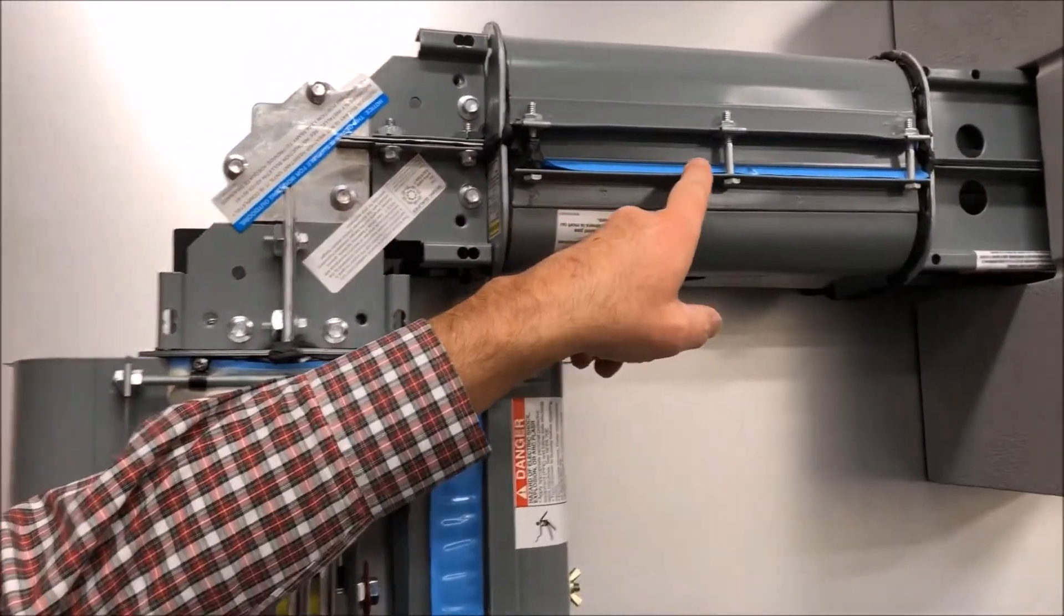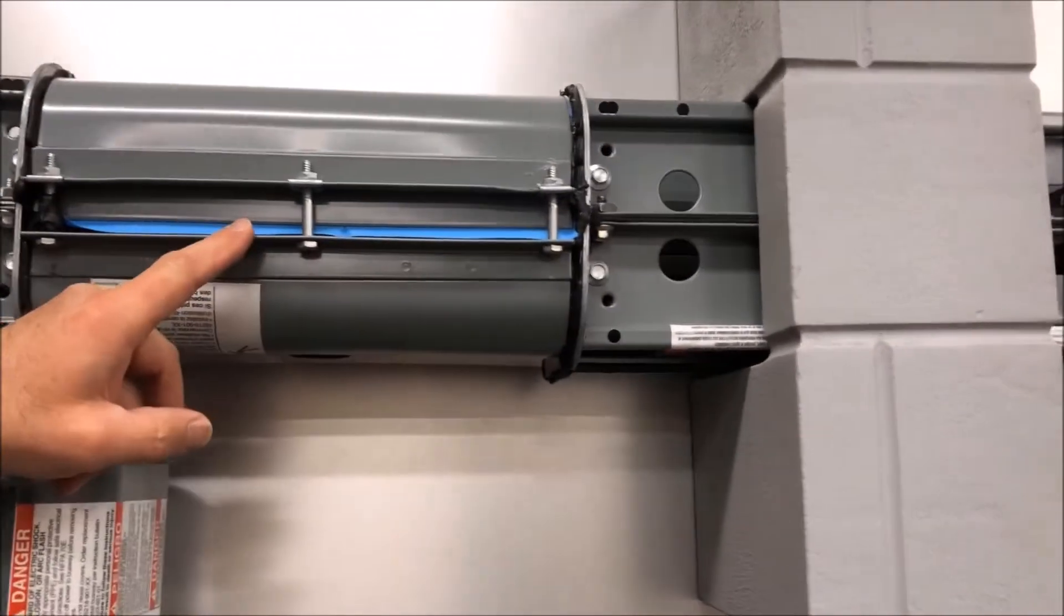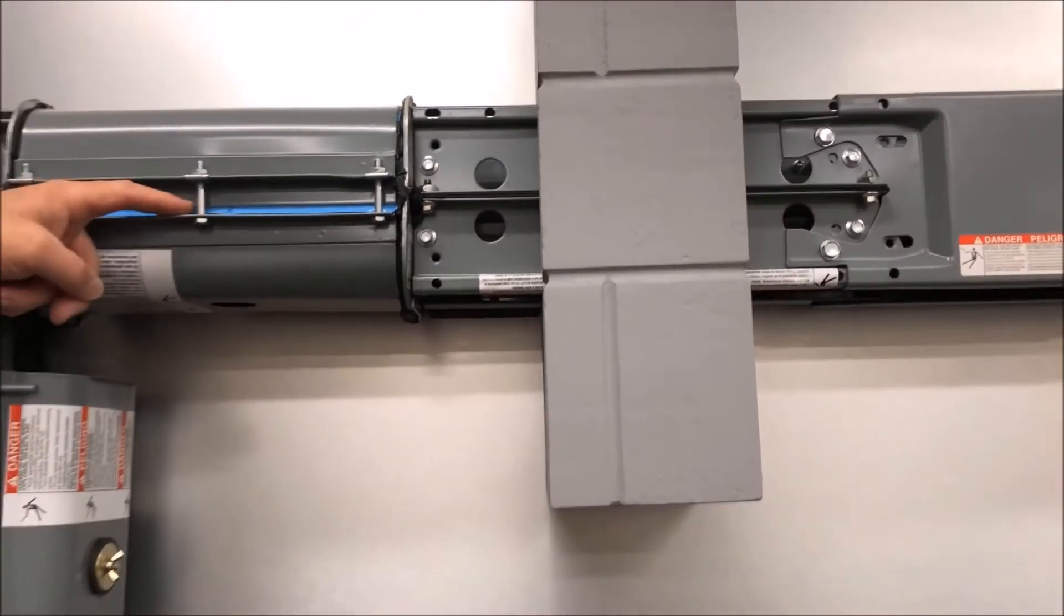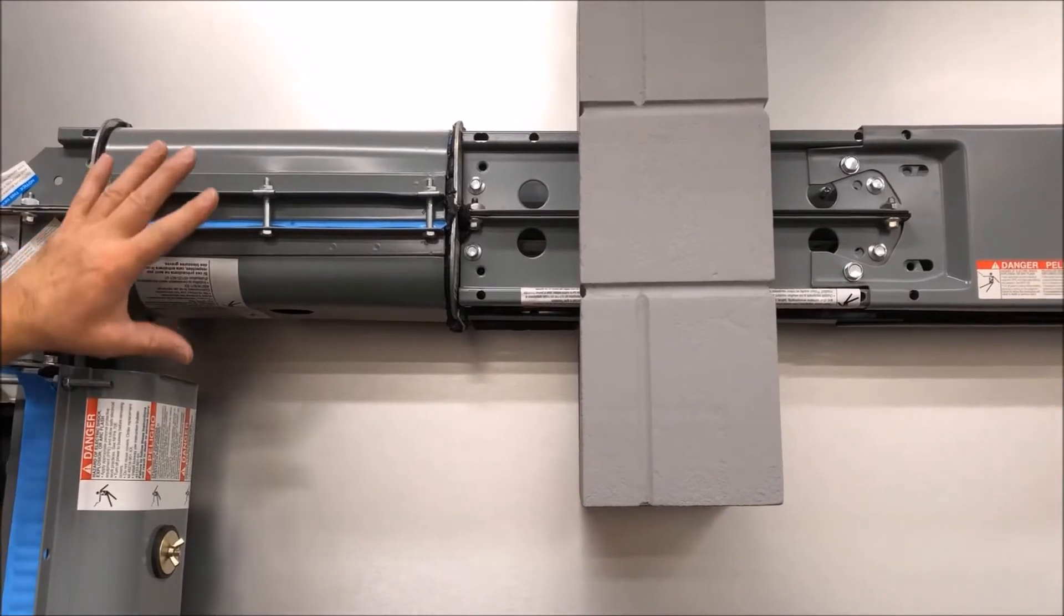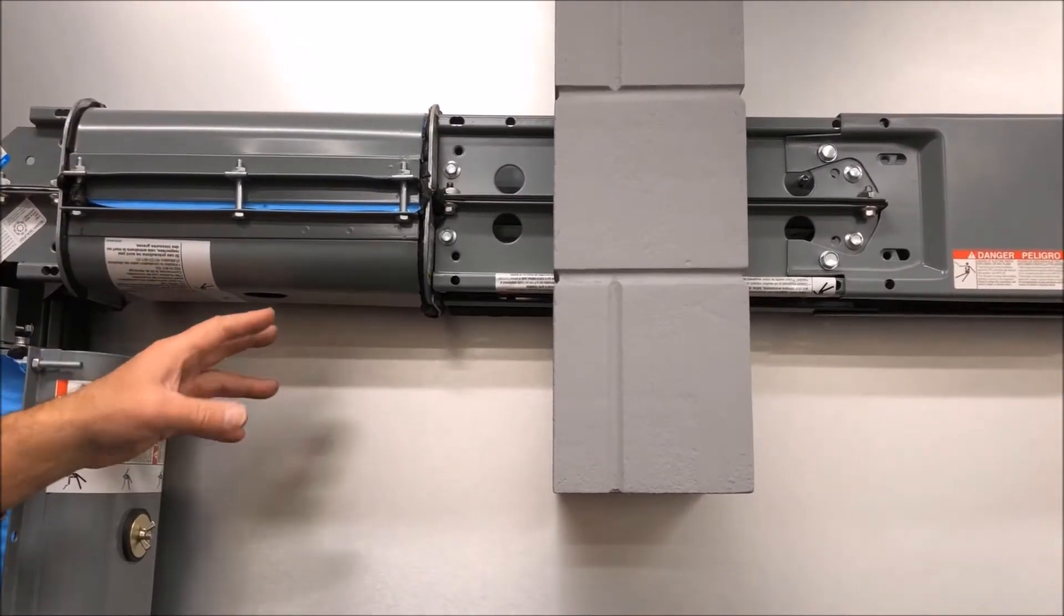This outdoor joint is assembled correctly, except this blue tape should not be there. That should just be the black butyl rubber. They did that for display purposes only. The drain hole is here, so this is all outdoor busway.